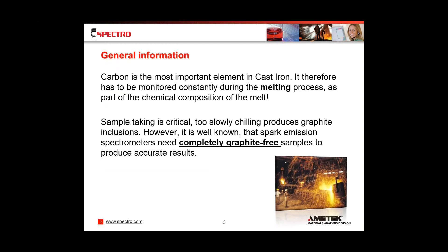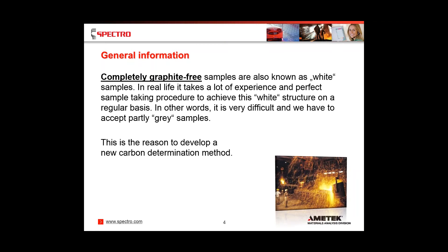Carbon, as you all probably know, is the most important element in cast iron. It therefore has to be monitored constantly during the melting process as part of the chemical composition of the melt. Sample taking is critical. Chilling too slow produces graphite inclusions. It is well known that spark emission spectrometers need completely graphite-free samples to produce accurate results. Completely graphite-free samples are also known as white samples. In real life, it takes a lot of experience and perfect sample taking procedure to achieve this white structure on a regular basis. In other words, it's very difficult and we have to accept partly gray samples. This is the reason to develop a new carbon determination method.